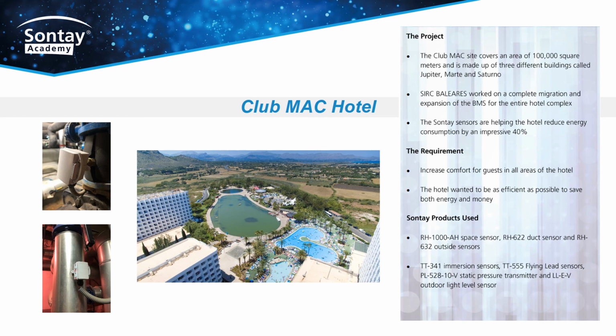Front of house systems, particularly in guest rooms, need to be both unobtrusive and tamper resistant. The overall scheme needs to have reliable sensing technology in multiple locations to ensure that the control scheme can accommodate differing occupancy patterns, depending on seasonal demands. Back of house systems, such as kitchens, also rely on accurate sensor data to ensure optimal operation of ventilation systems. As an example, reducing ventilation rates when cooking is producing fewer fumes or during quieter periods.